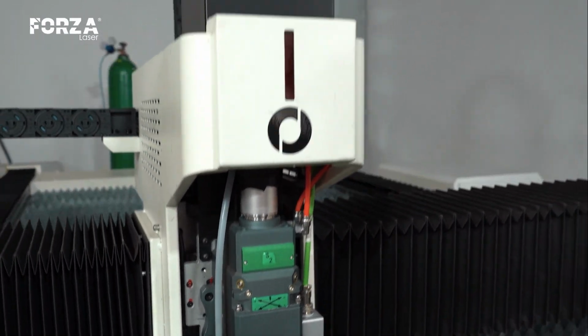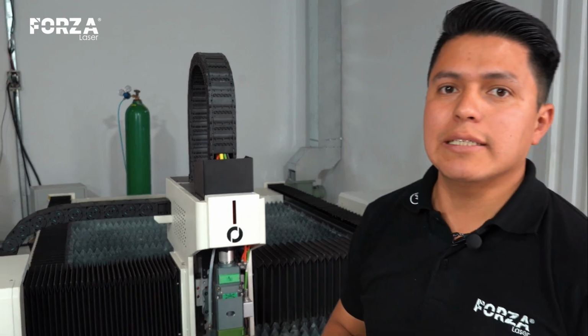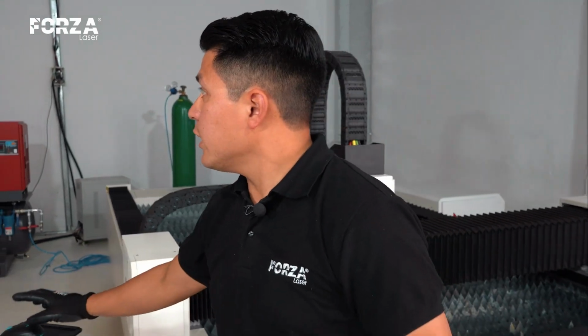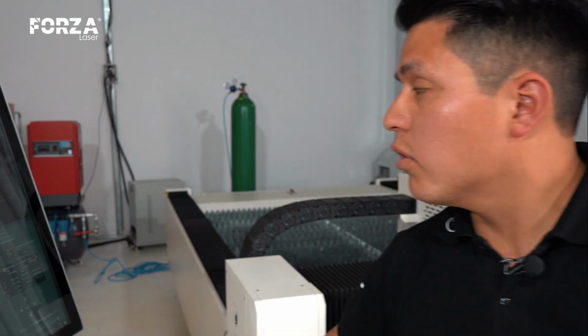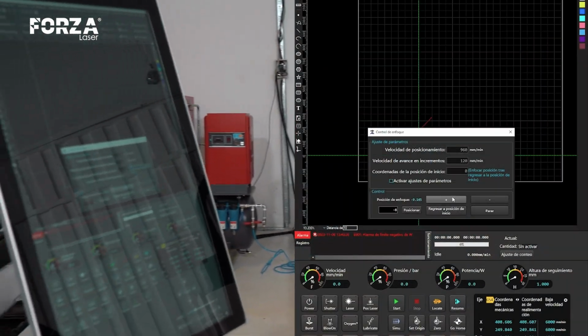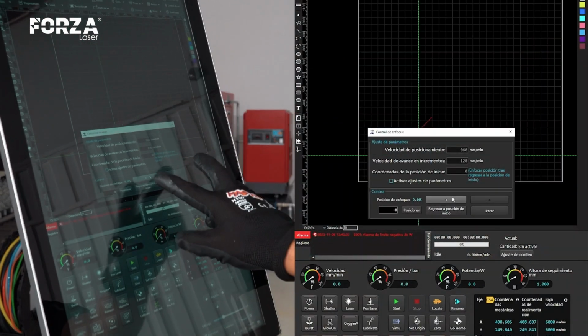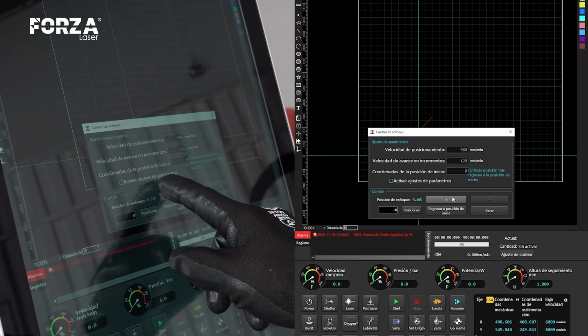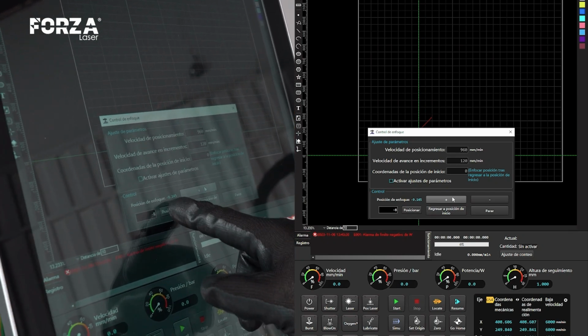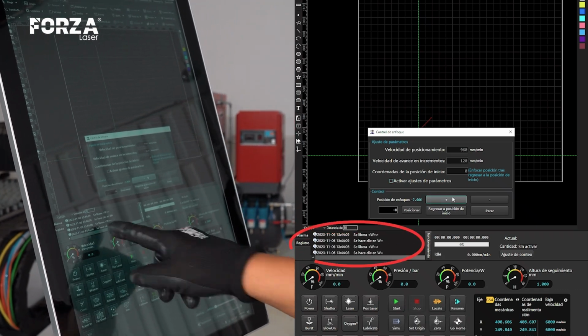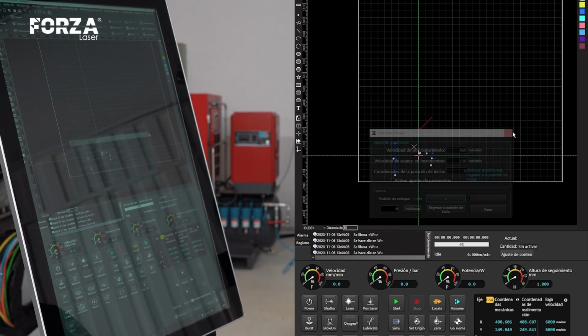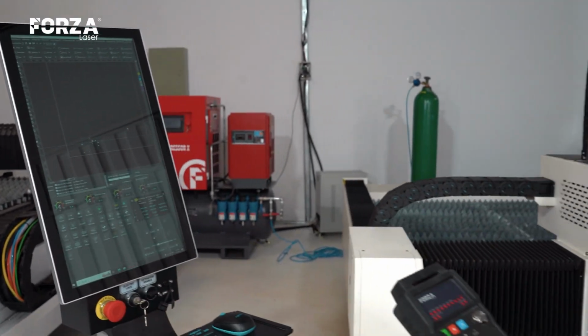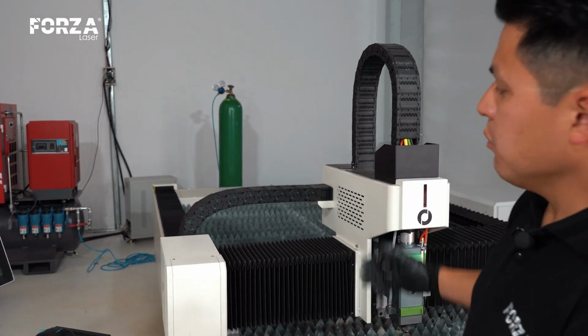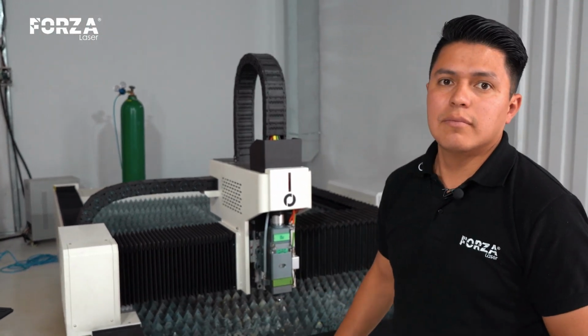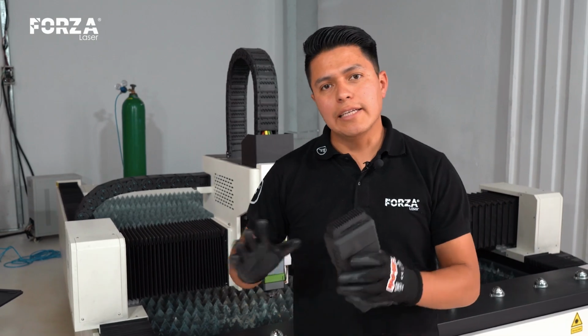To resolve this particular alarm, we're going to carry out the following procedure. We navigate to focus control and click on that particular button. Here, we essentially have to perform one of two actions. We first observe precisely where the fault occurred in this specific case. It's indicating a negative value. So, we then press the plus button here, continuing until it clears the error. Once it's out of the error, we then perform the normal process of finding the equipment's 0 point. And that, right there, is precisely how you fix this error.